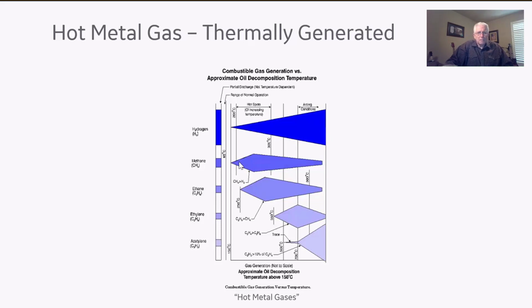The next one, methane, generates up until you hit about, I don't know what temperature that looks like to me, but this is about 150. This starts at 250, which is ethane. So it looks like it begins to break off somewhere in the neighborhood of maybe 300 degrees, or 275, I don't know. Neither of those temperatures is good, but take your pick. So you're above 200, 250 degrees C here when you begin to actually break this gas. And then you have ethane, which will do a buildup and then a break. And then ethylene begins to generate at 350 degrees C.